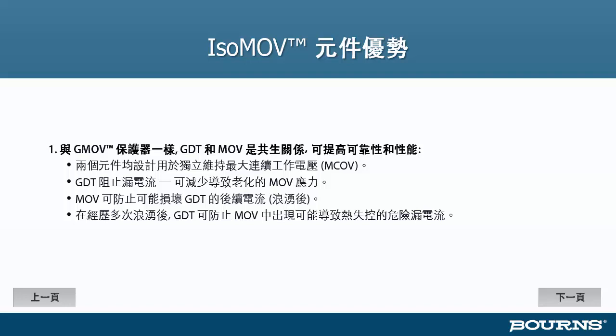Both elements are designed to sustain the maximum continuous operating voltage so that if the other element fails for any reason, you still have a line voltage rated part that will continue to protect the load. What's really useful in the relationship between the two is that the GDT blocks any leakage currents that would normally be flowing through the MOV, drastically reducing the stress on the MOV, which could cause premature aging of the MOV.